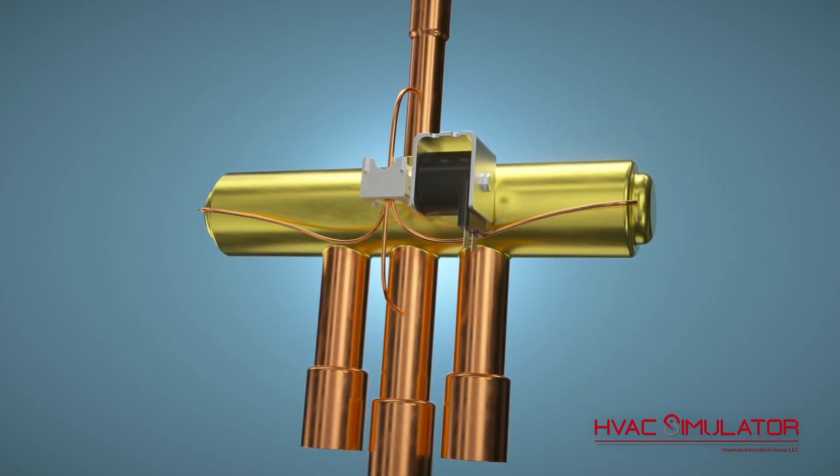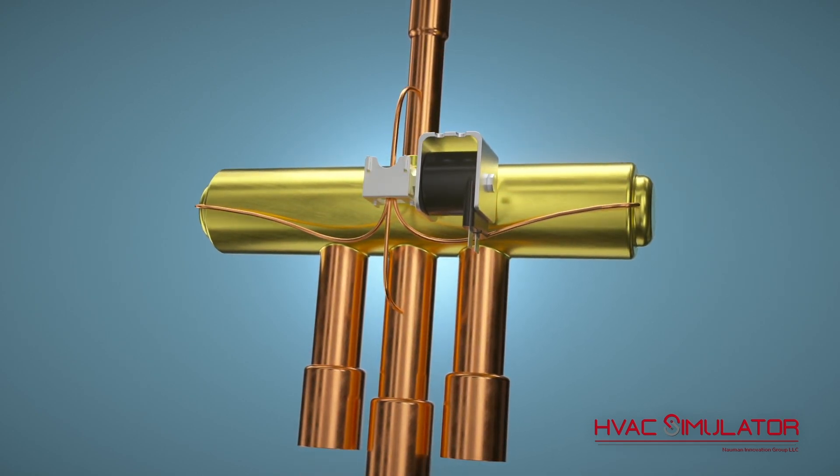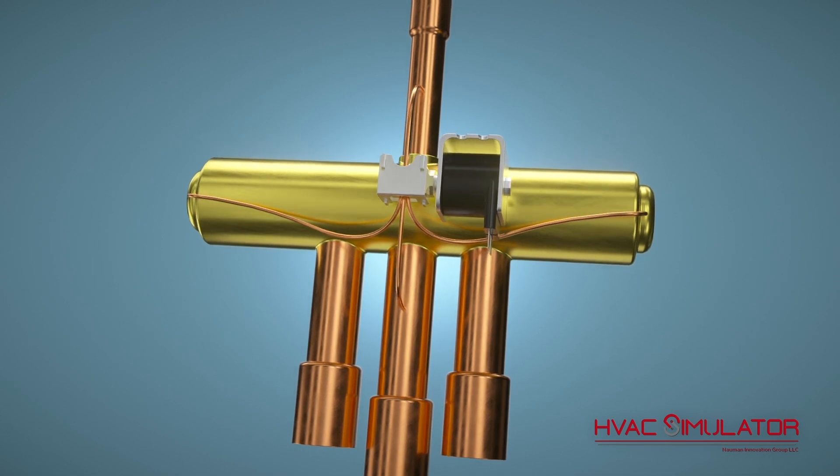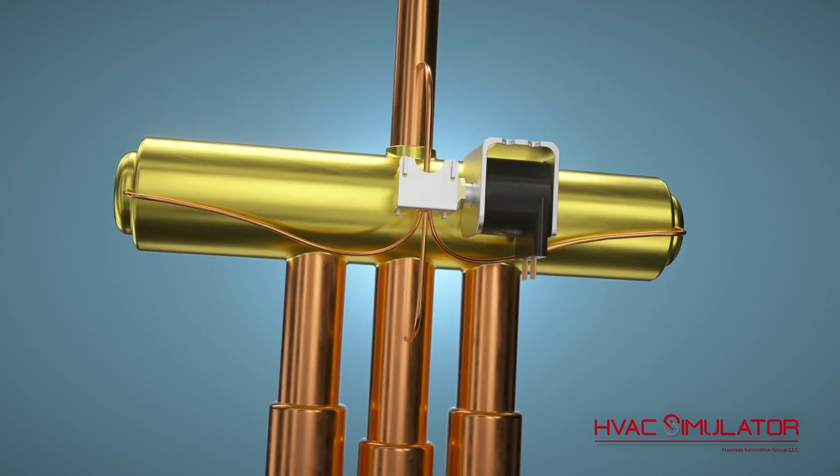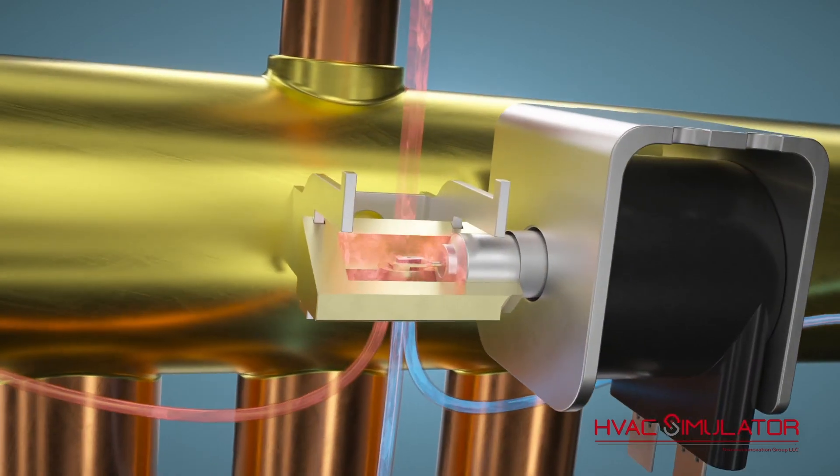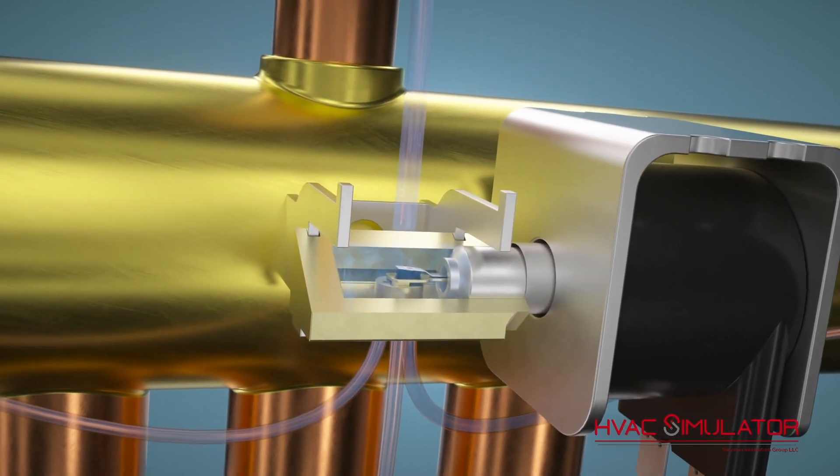When the thermostat satisfies the cooling call, the contactor at the heat pump de-energizes, but the solenoid stays energized. Without the discharge pressure from the compressor, the valve on the stem opens and equalizes all the pressures in the reversing valve.